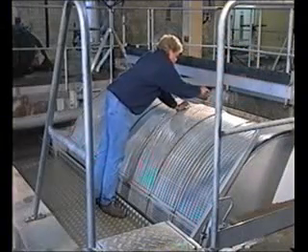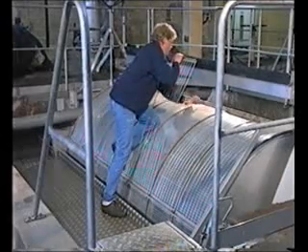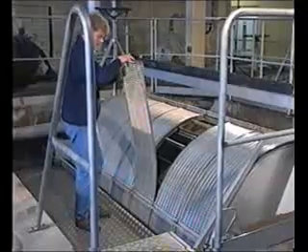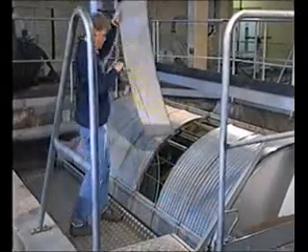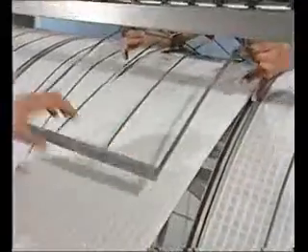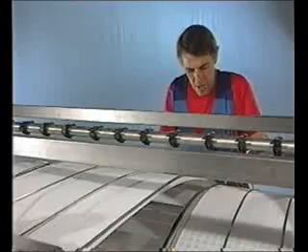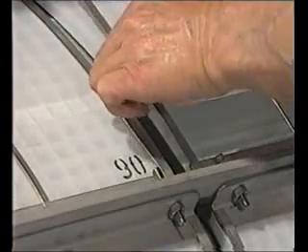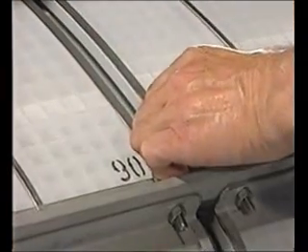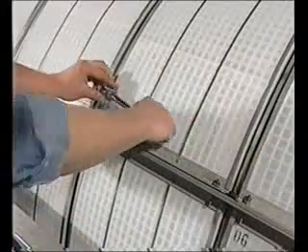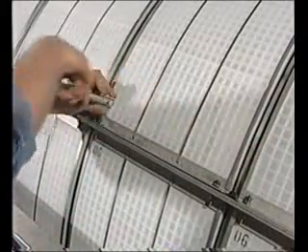The drum filter consists of a drum which is constructed in sections and, depending on the diameter, can have a varying number of filter panels fitted around each section. The drum filter panel is 1200 by 400 millimeters, manufactured in polypropylene and polyester or stainless steel cloth. It is constructed to be flexible so that the filter panel can be mounted onto small or large drums.